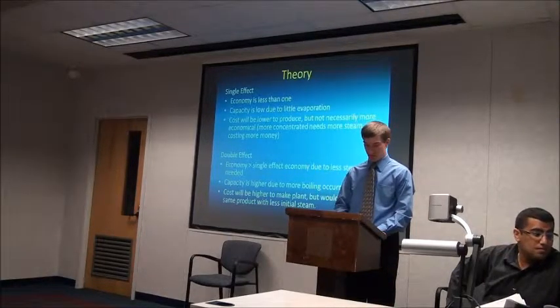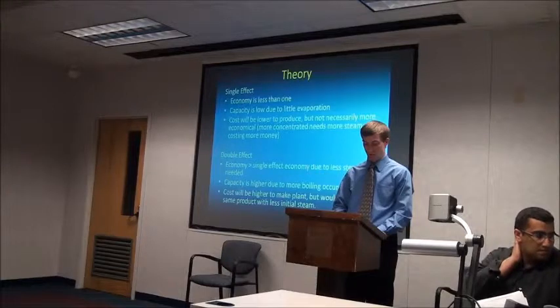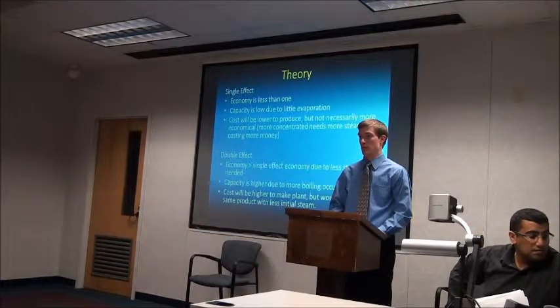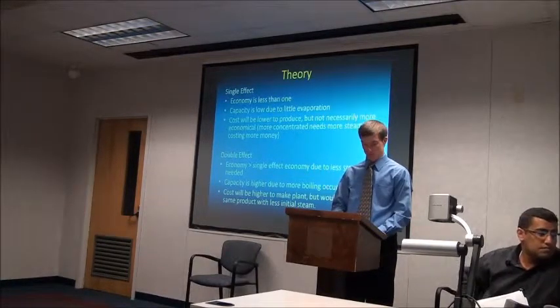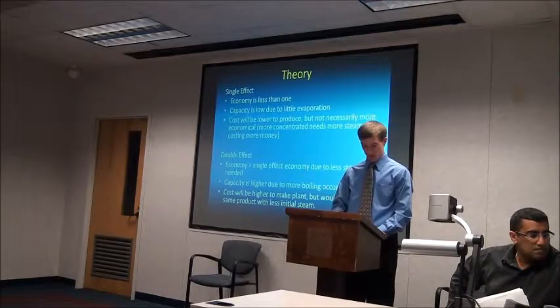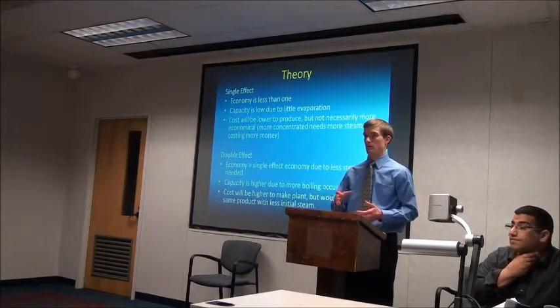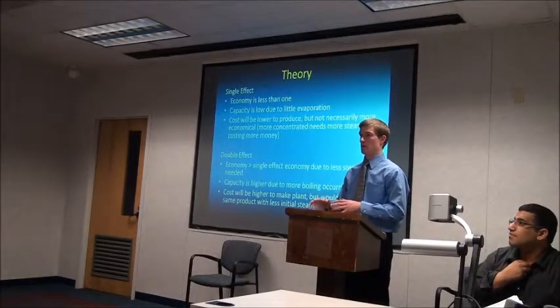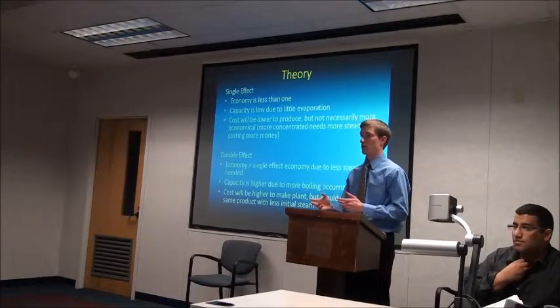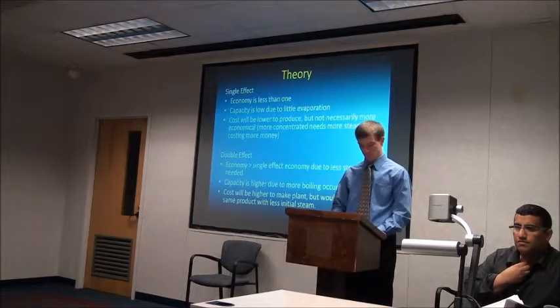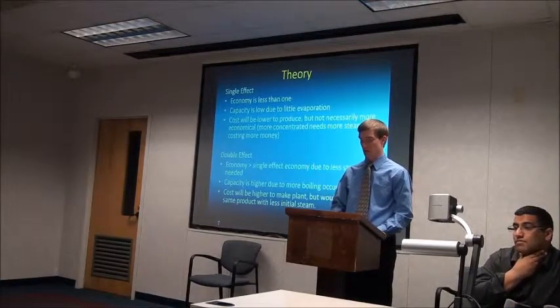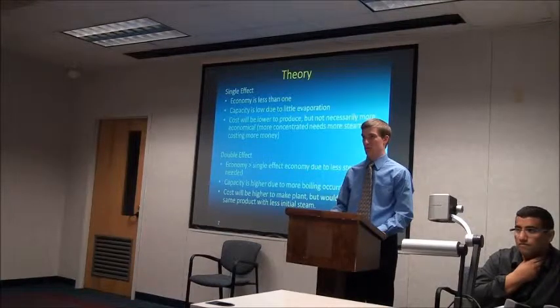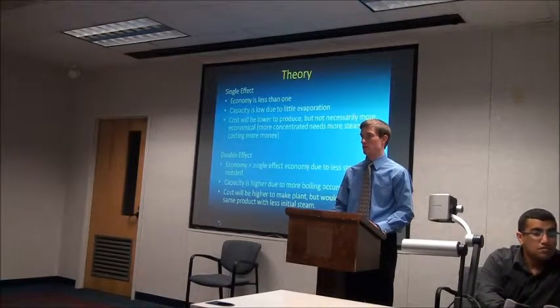With a double effect, we would expect the economy to be greater than a single effect, because there is more evaporation occurring — steam is recycled from the first effect. The capacity is higher due to more boiling occurring: the first effect boils some vapor out, which then goes to the second effect where more vapor can be produced. Even though the cost is higher to build the plant — $200,000 in our case — it would require less initial steam, so the operating price would be a little less.